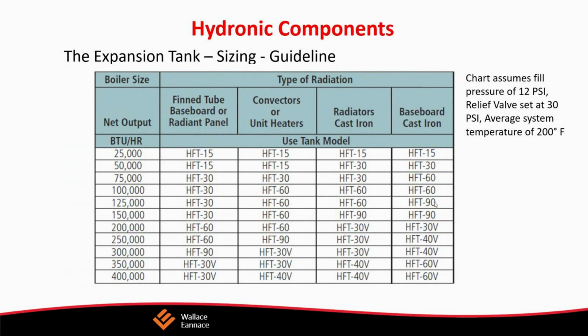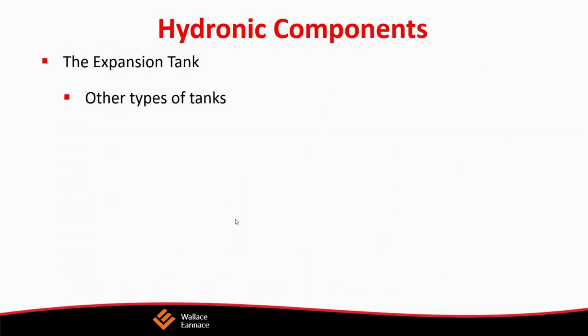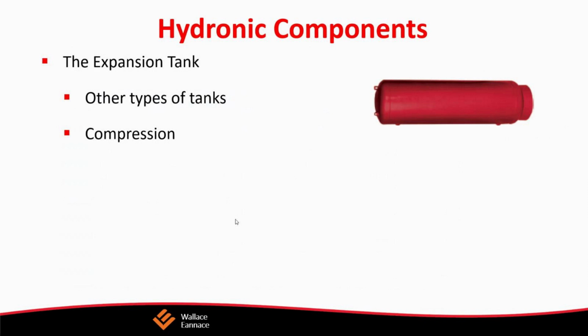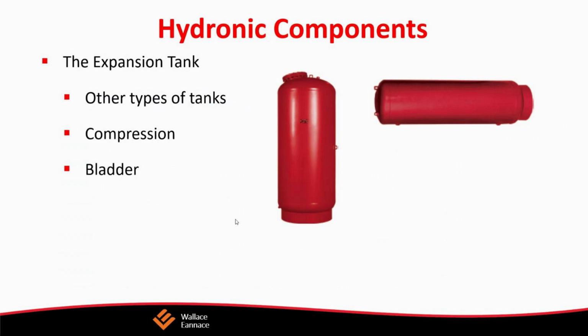Okay, let's start talking about other hydronic components, and let's consider the expansion tank. We've talked enough about pumps, I think, at this point. So the expansion tank, what does it do? Well, and what is it? How does it work? How do we size it? And where do we put it? What does it do? Well, raising water temperature in a heating system from 40 to 180 increases the volume of water by about 5%. The expansion tank absorbs this thermal expansion. That water needs to go somewhere.